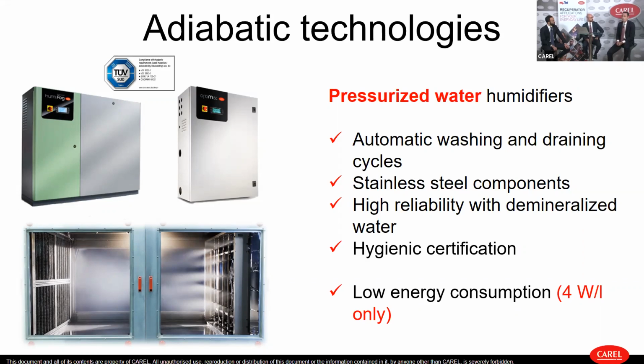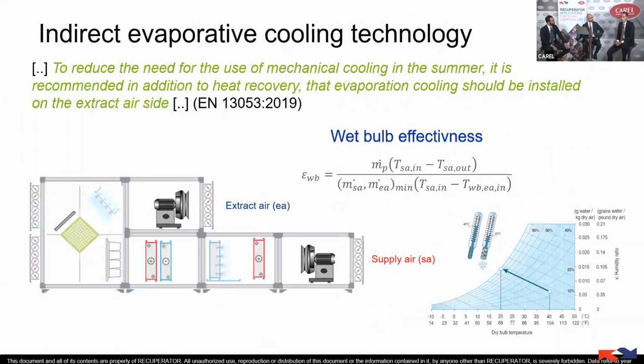One of the solutions that we would like to promote is indirect evaporative cooling technology. We already explained that adiabatic humidifiers can be used to regulate the level of humidity on the supply side, but at the same time we can use the same pressurized water atomizer that we use for humidification also for controlling the temperature on the extract air, without affecting the humidity on the supply side.